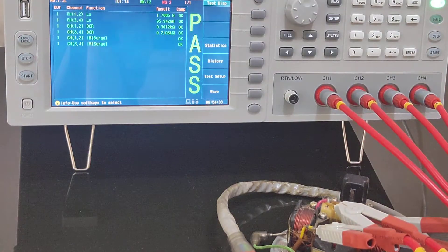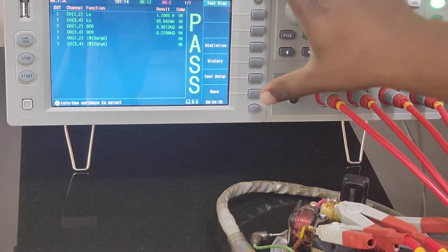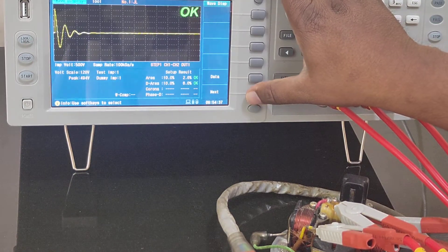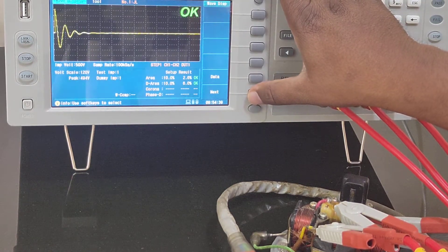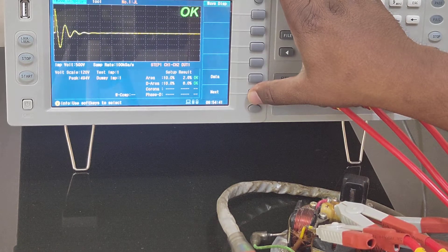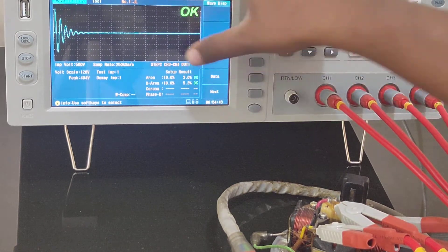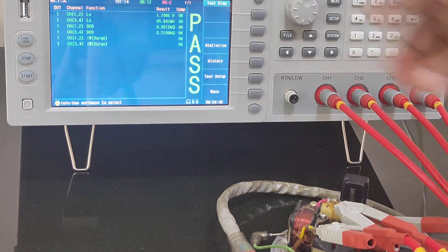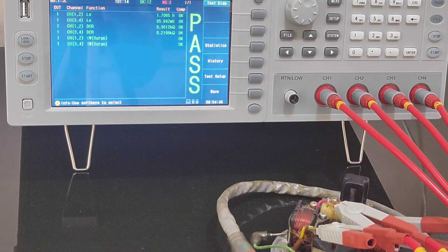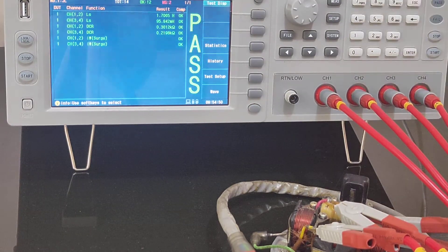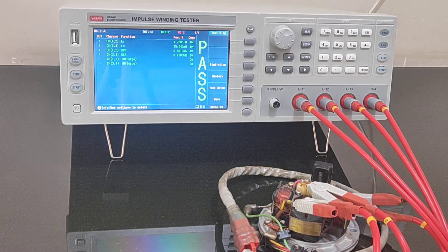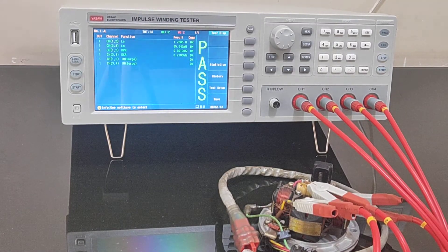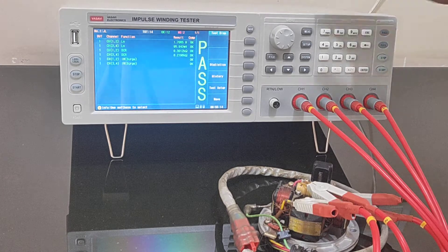Like that you have DC resistance and this is impulse winding. If you also wanted to see the waveforms you can check it over here. This is channel 1 to 2, this is 3 to 4. Like this you have two waveforms.